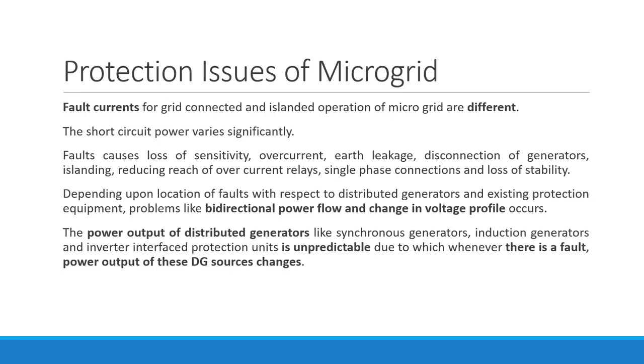Depending upon the location of faults with respect to distributed generators and existing protection equipment, problems like bidirectional power flow and change in voltage profile may also occur. Bidirectional power flow: maybe the power should flow from A to B, but it started flowing from B to A. This is happening due to the fault, possibly. The voltage profile: receiving end voltage is greater than sending end voltage, or maybe there is a dip in the voltage. You have studied the voltage profiles. So that is possible.